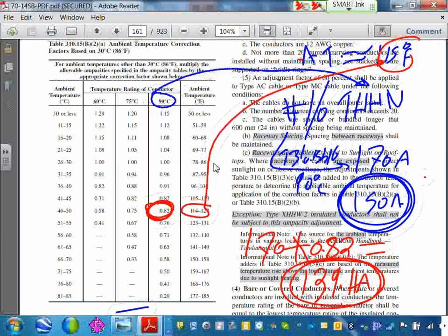That's it. So we go to that first table, the 16B, get the amps, then go to that table? Yes, if you have the conductor. First, you go to the first table to find the amp under the 90 degree column, if it's 90 degree. If it's 75, you have to go to 75. But this is THHN, so 90. We use 90 because we know the insulation is rated for 90, which is 99% of the time.